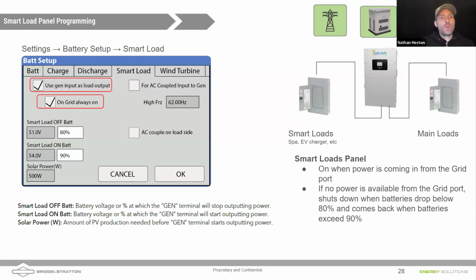If you use the generator input as a load output, that's where you would have power to the sub panel based on battery percentage. Notice in the bottom left corner of that menu, you see an 80% and a 90%. So when the batteries get below 80%, it's going to kill that sub panel, right? It's going to turn off those loads because those are not important loads for you in a grid outage event.